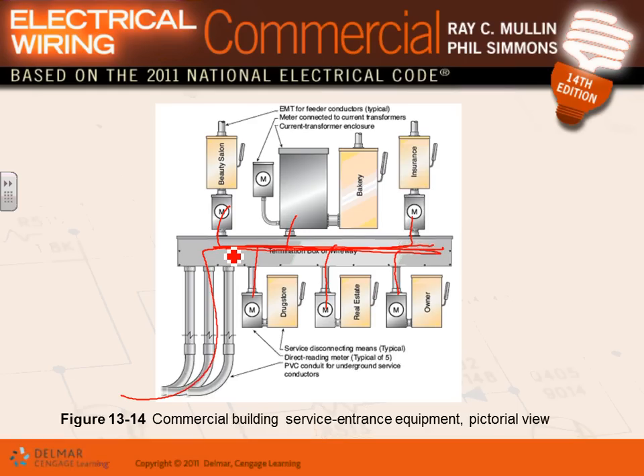it. I will bring to attention the CT cabinet here and the meter. If it's higher than 200 amp, these are 200 amp. Higher than 200 amp, you have a CT cabinet here just to convert the amps into a lower amps where the meters can handle. Mistake number one, next time you put the disconnect after the meter, not before the meter. You don't disconnect the meter.